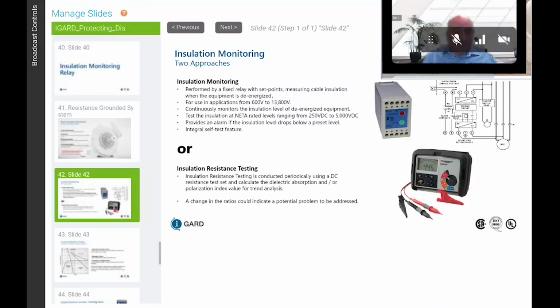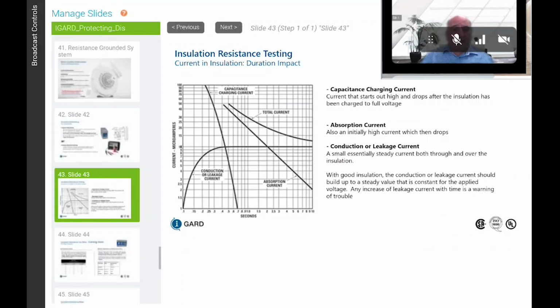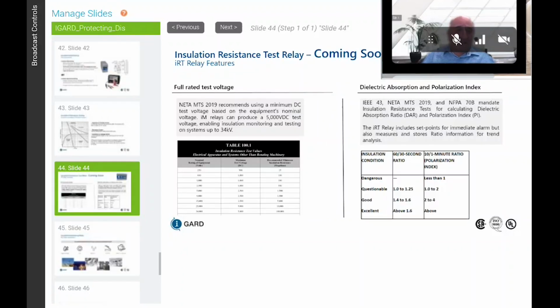So we inject the voltage onto the bus and measure how much current is on the bus. We're looking at a couple of things: the capacitive charging current, the absorption current, and the conduction current. With this curve we ensure the insulation resistance is good. For medium voltage we inject 5,000 volts, and the insulation monitor can produce 5,000 volts and enable insulation monitoring and testing up to 34 kV. What we're looking at is the absorption ratio and the polarization index, and we have to make sure these are held within tolerances. So we're looking at deterioration over time and repeatability of the test.